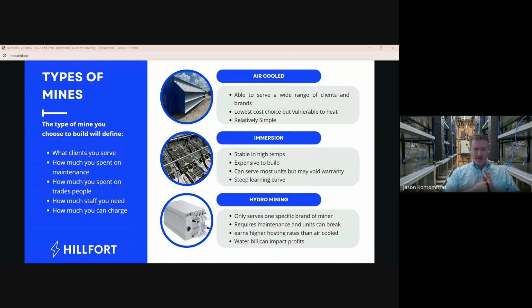A typical target for building an air-cooled facility is going to be 160 to 250,000 a megawatt, and that's if you buy the best equipment, go completely overkill on everything, using American transformers, the whole 9 yards. But there's reasons that immersion is more expensive.